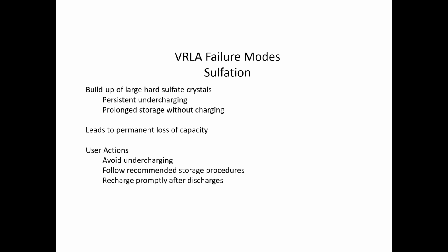So that's, like I said, more common than what we find, but we do occasionally find faulty rectifiers or chargers that are set wrong or actually failed or lost their ability for regulation and then undercharge a battery. There's not a lot you can do for that. That is where equalization could be utilized to help drive those sulfates off the plates. But like I said, for the most part, if left too long, it's permanent damage. It's very hard to recover from a battery that's been stored for 3-4 years, whatever, without being charged. They're usually not recoverable.